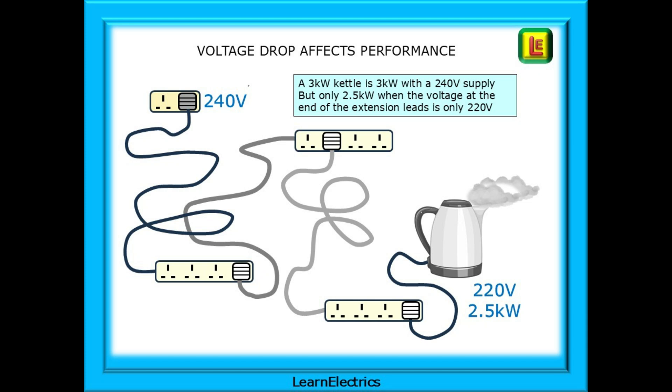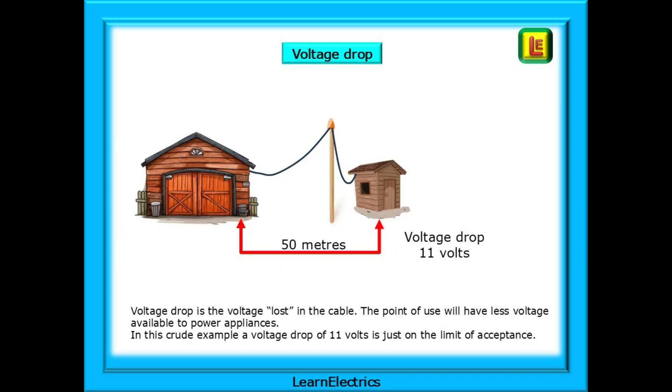In our example, if it took two minutes to boil a full kettle of water at 240 volts, it could take almost two and a half minutes to boil the same volume of water at the end of the extension leads. Many people will not realise that voltage drop is the voltage lost in the cable. The points of use will have less voltage available to power appliances, and they will happily do a DIY job and loop a long cable to the shed at the bottom of the garden. The longer the cable, the greater the voltage drop. In this crude example, perhaps a 50 metre elongation, the voltage drop of, say, 11 volts, is just on the limit of acceptance.